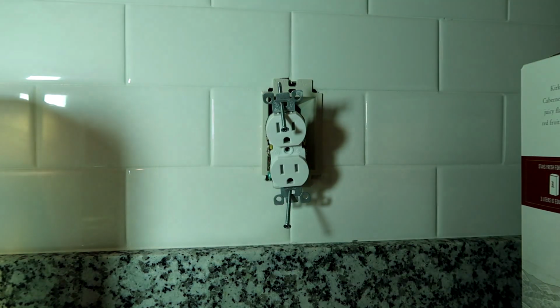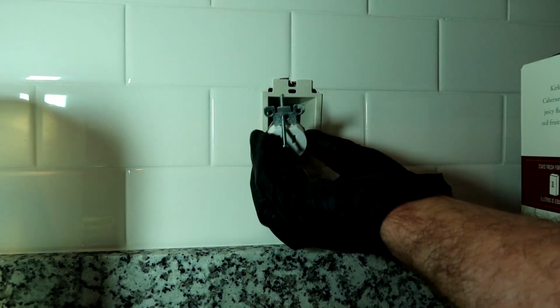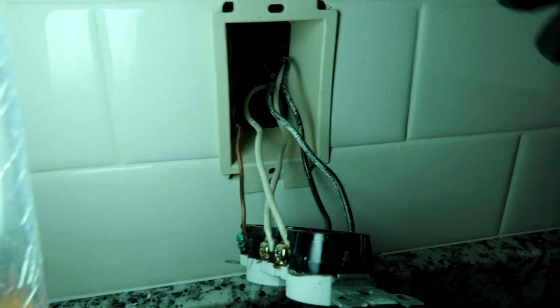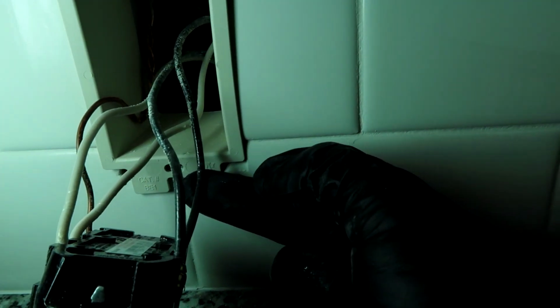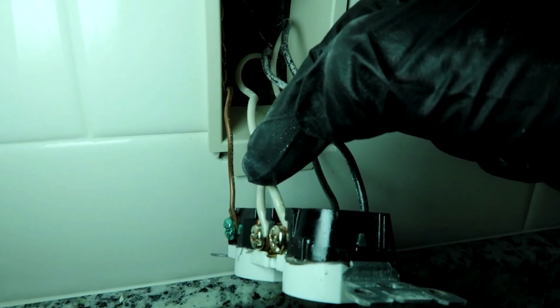It's dead. I don't see any loose neutrals or anything. Not yet. Alright, looks like they tried to throw old Skid a curveball. I think I see the problem here. Old head smasher if you were new to the biz. So this black wire on the bottom here is coming out of the same sleeve back here as this one, but it's wired to the top.